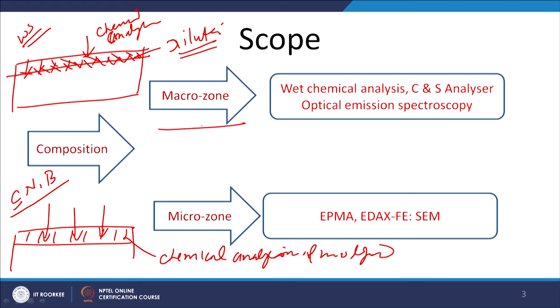It can vary from 5 to 10 mm, including thousands of micro constituents present on the surface of the modified component. When it is required to perform the chemical analysis of the micro constituents individually or over a very small area, that is called chemical analysis of micro zones, and for that purpose we can use the electron probe micro analyzer or energy dispersive X-ray analysis with the help of FESEM.